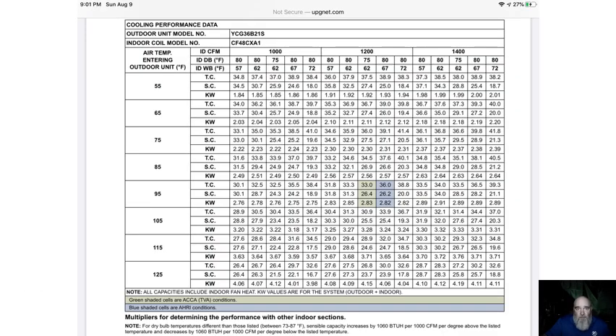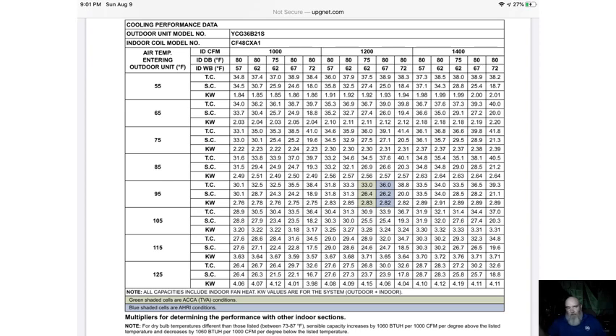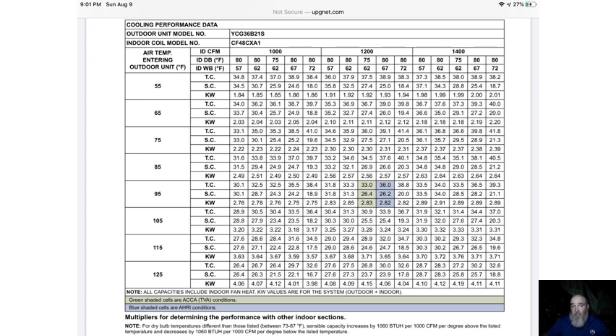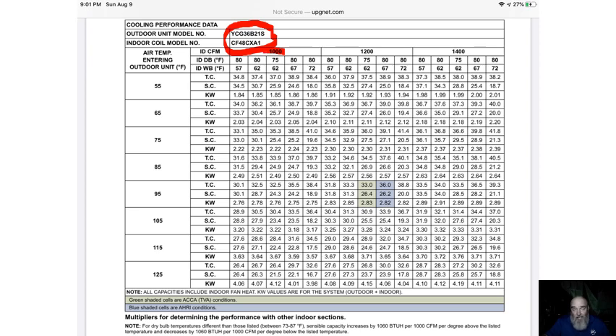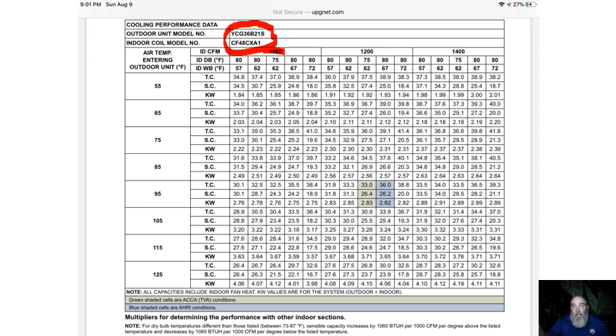What we have in front of us is a piece of manufacturer's extended performance data. You might call it application data. There's several names for it, but this is where the rubber meets the road. It's showing a nominally sized 3-ton outdoor unit and a nominally sized 4-ton evaporator coil. I keep saying nominally sized because that's what it is, not the actual size. The actual size of this combo, if we were to run it at 1,000 CFM, it's not out of the question to be running a 3-ton piece of equipment at 1,000 CFM if we have a house that needs that.